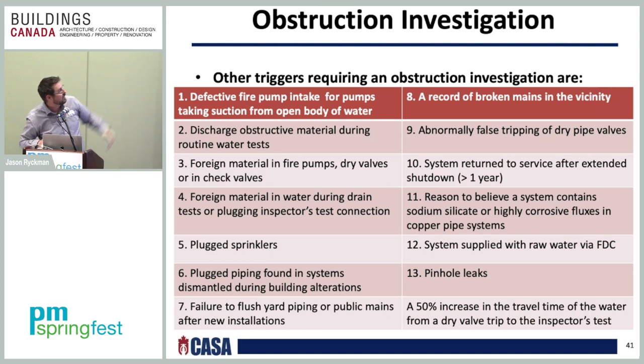You have a defective fire pump intake, or a fire pump taking suction from an open body of water, which would be a trigger to have an obstruction investigation. Discharge of obstructive material during routine water tests. Foreign material in fire pumps, dry valves, or in check valves. Foreign material in water during drain tests or plugging of inspector's test connections. Plugged sprinklers. Plugged piping found in systems dismantled during building alterations. So if you see stuff like that during building alterations, that can trigger an obstruction investigation. Failure to flush yard piping or public mains.